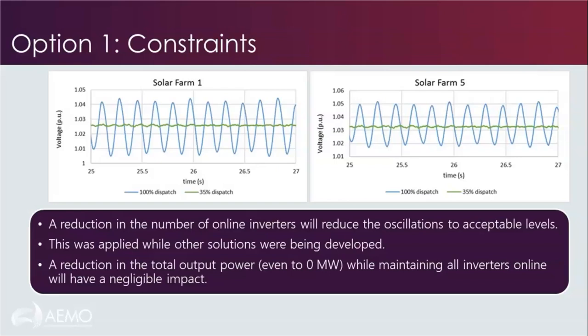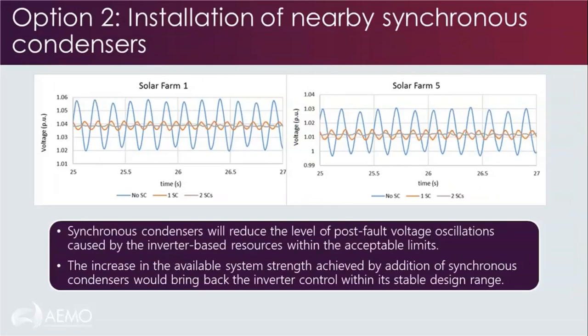Moving to the second mitigation measure, which is the installation of synchronous condensers. As I mentioned earlier, in this particular instance, there were no nearby synchronous generators. There were some within a few hundred kilometers, but considering the weakness of the network, those high impedances effectively create a fictitious filter that does not allow the system strength, or fault level, whichever metric we use, to pass through from one location to another. So you would need a local solution, and the best available was the application of synchronous condensers.